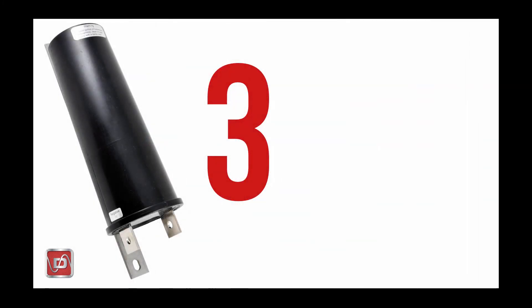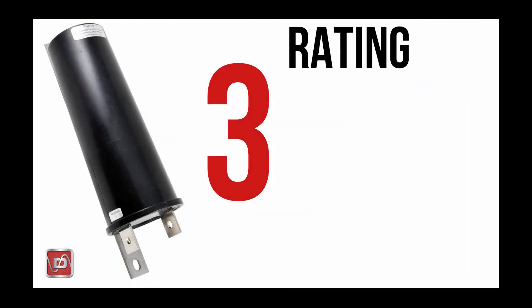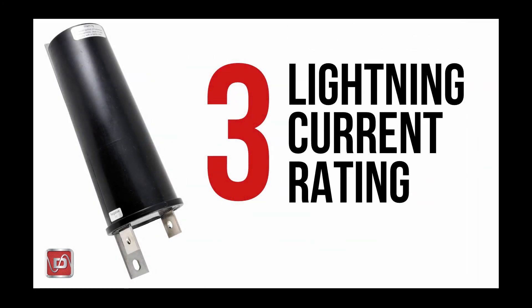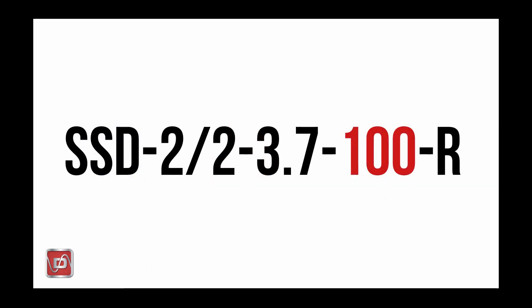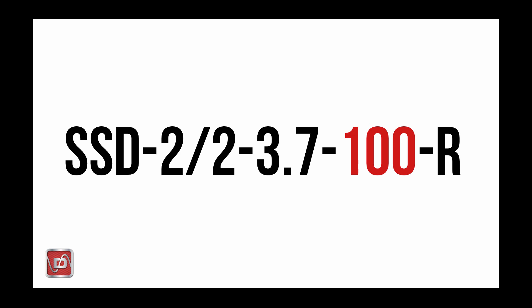The last of the three primary ratings for Dairyland decouplers is their lightning surge current rating. All Dairyland products have a lightning surge current rating, most commonly 100ka, which is designated in most model numbers as simply as 100 if it is shown. This is not a configurable item, however, and is dictated by other product ratings that you choose and other product construction. Only the smallest SSD and OVP2 products have a lower 75ka lightning current rating.